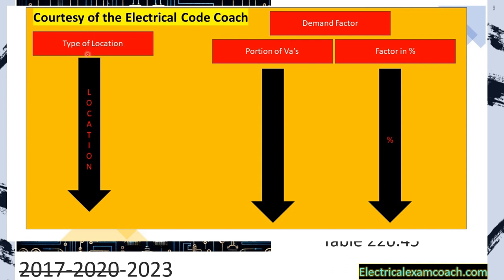On the left-hand side of the table is our type of location. You'll notice dwelling units, hotels and motels, warehouses and storage, and then a very important one at the bottom that says all other locations. So unless it's one of these locations listed above, it does not count. Dwelling units are the only one on this list that includes the receptacles as well. Everything else in this is just for lighting only.